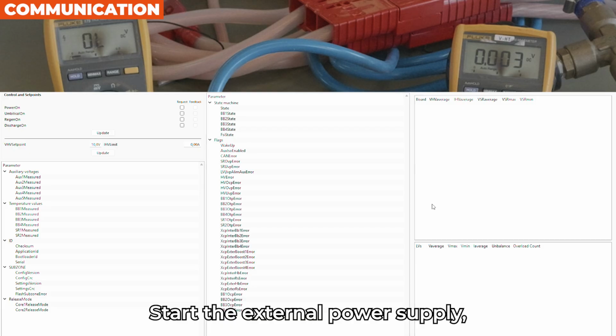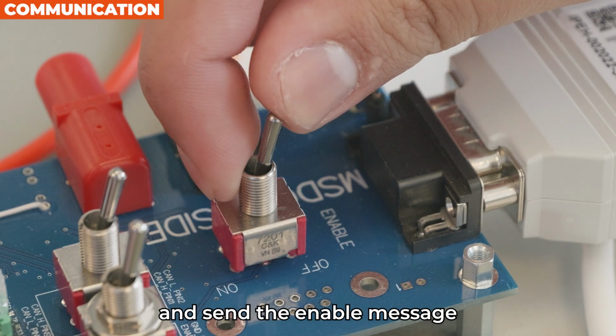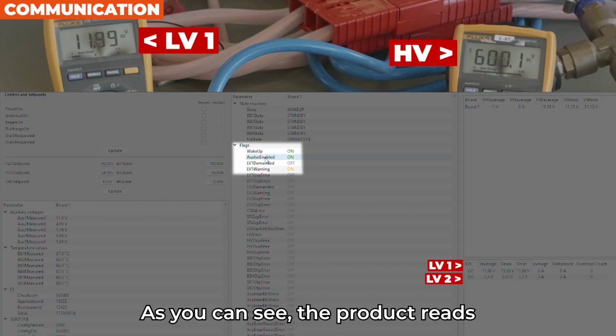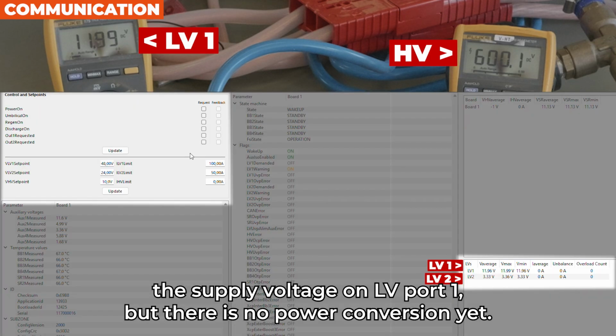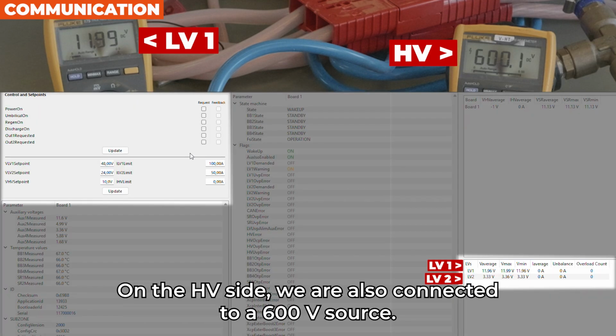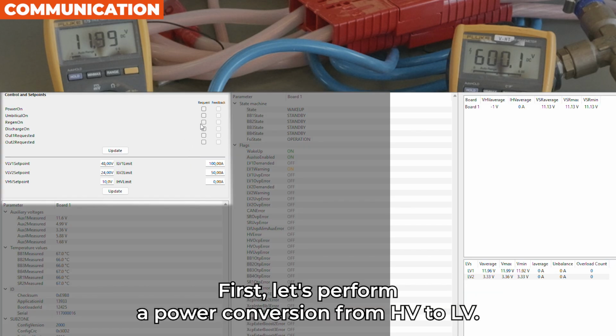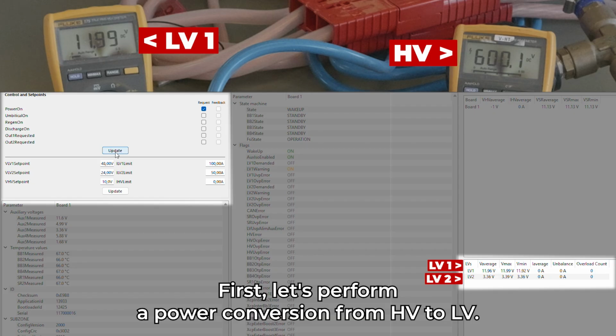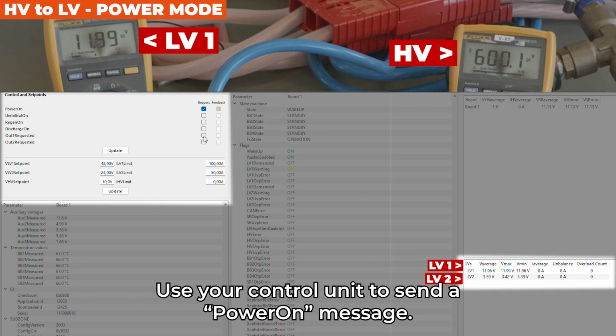Start the external low-voltage power supply and send the enable message. As you can see, the product reads the supply voltage on LV port 1, but there is no power conversion yet. On the HV side, we are also connected to a 600-volt source. First, let's perform a power conversion from HV to LV. Use your control unit to send a power on message.